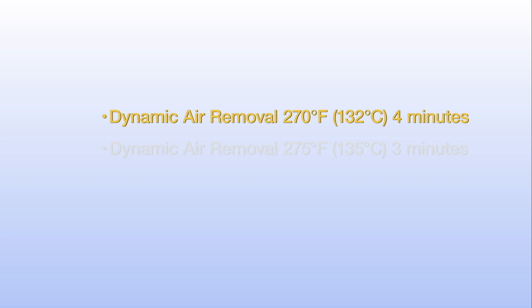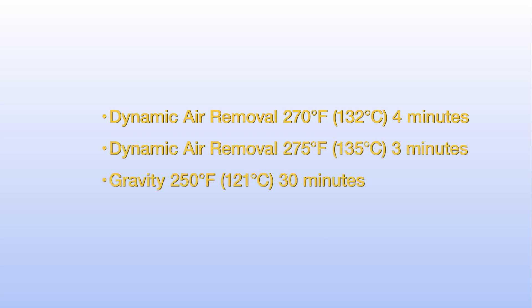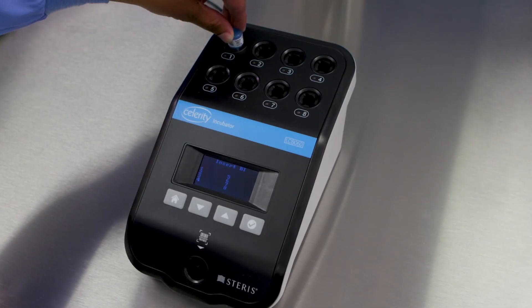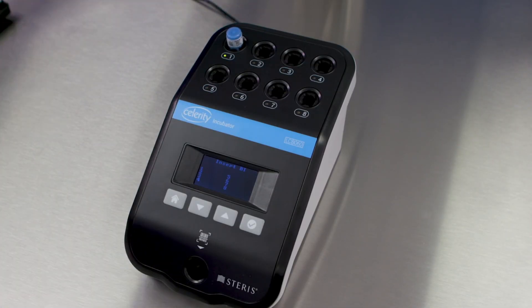The Celerity 20 STEAM Biological Indicator is used for routine monitoring, qualification testing, load monitoring, and product testing of steam sterilization cycles shown on the screen. When used in conjunction with the Celerity Incubator, the incubator provides a fluorescent result within 20 minutes.